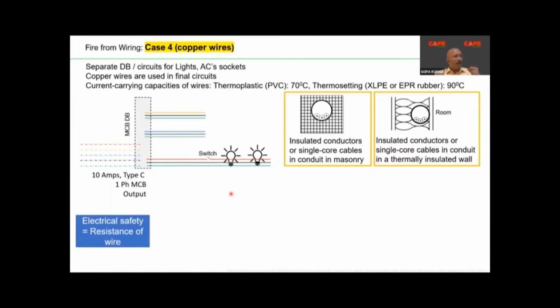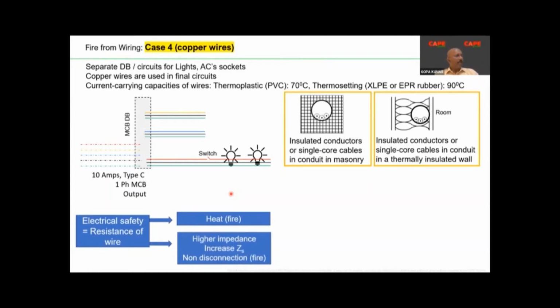Here, the most important point we should think about is the type of copper used in the wire. It is not the type of insulation, because the wire manufacturers always say safe wiring is FRLS, fire retardant low smoke, and zero halogen cables are more safe. But for fire safety, more than the insulation, the first thing is the resistance of the wire. The resistance is directly connected to fire, because if the resistance is higher, of course the heat is more and the chance of fire is higher. Higher impedance in a wire also leads to non-disconnection of an MCB. Very important. If you use a wire with higher resistance, that may lead to non-disconnection of a device. As you can see in the video, the fire started because the MCB didn't trip within its prescribed time.